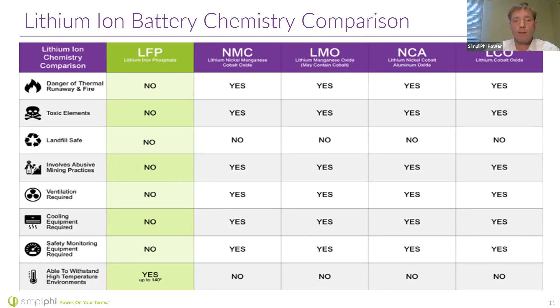In certain circumstances, AHJs may require safety monitoring equipment. I know New York City does require safety monitoring in terms of off-gassing, etc. And are these chemistries able to withstand high temperatures? The answer here is that LFP has the highest temperature range. The battery can be the hottest and still operating.